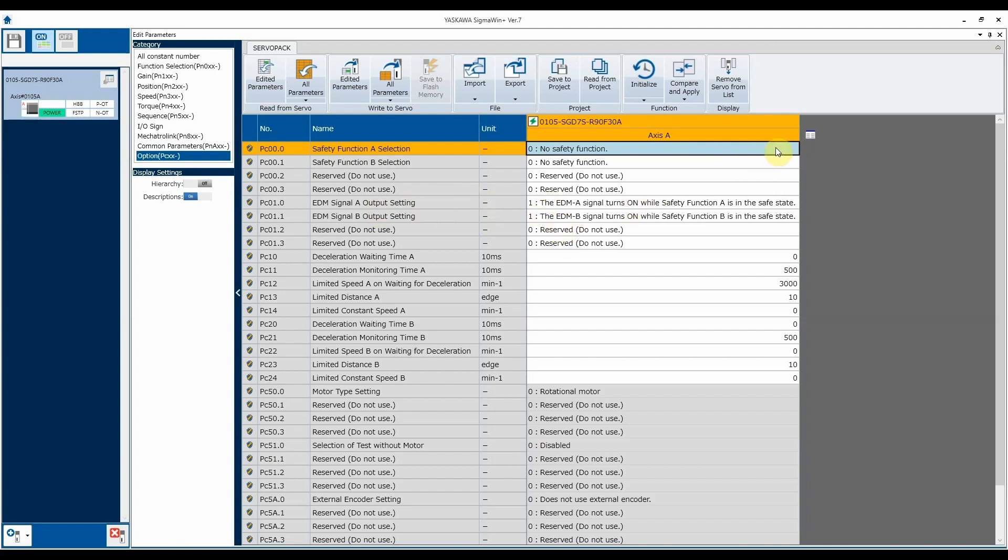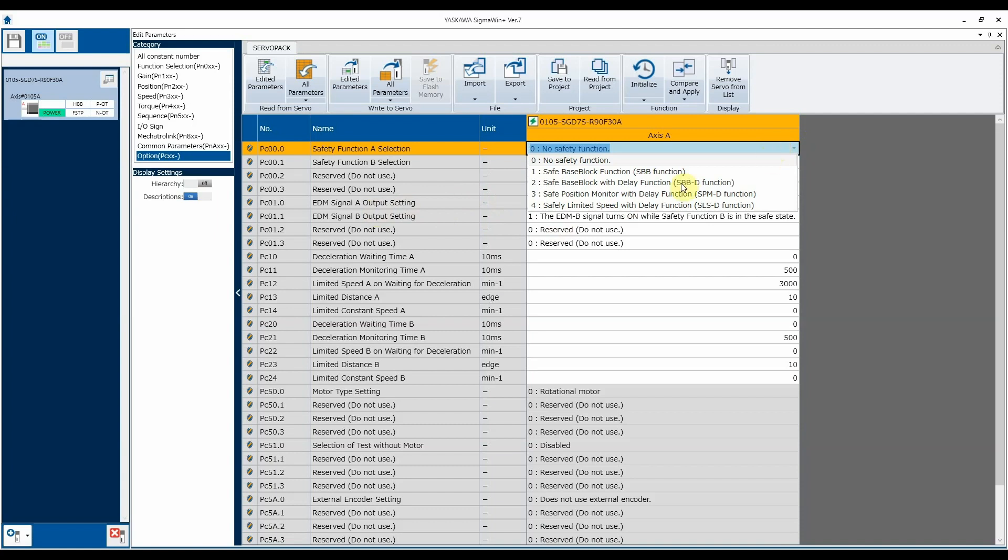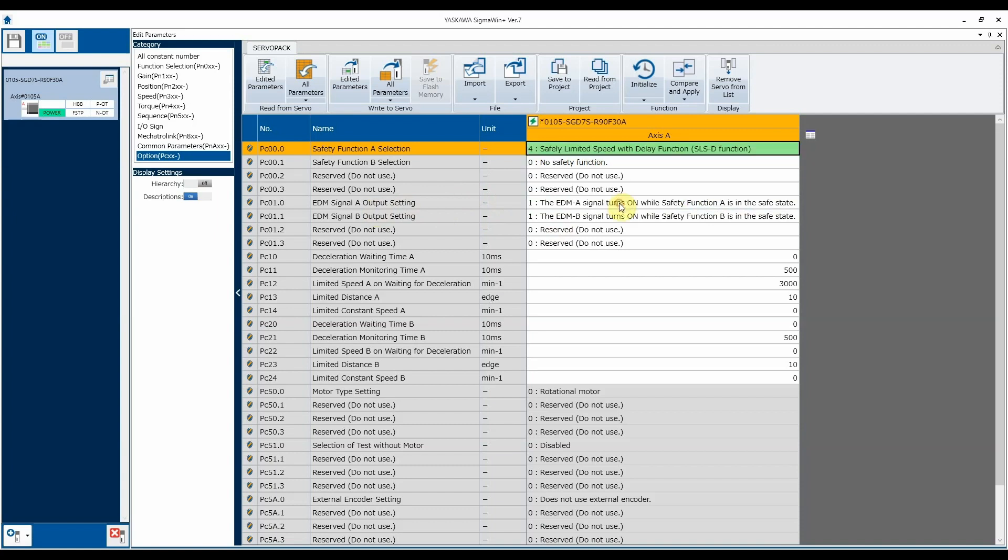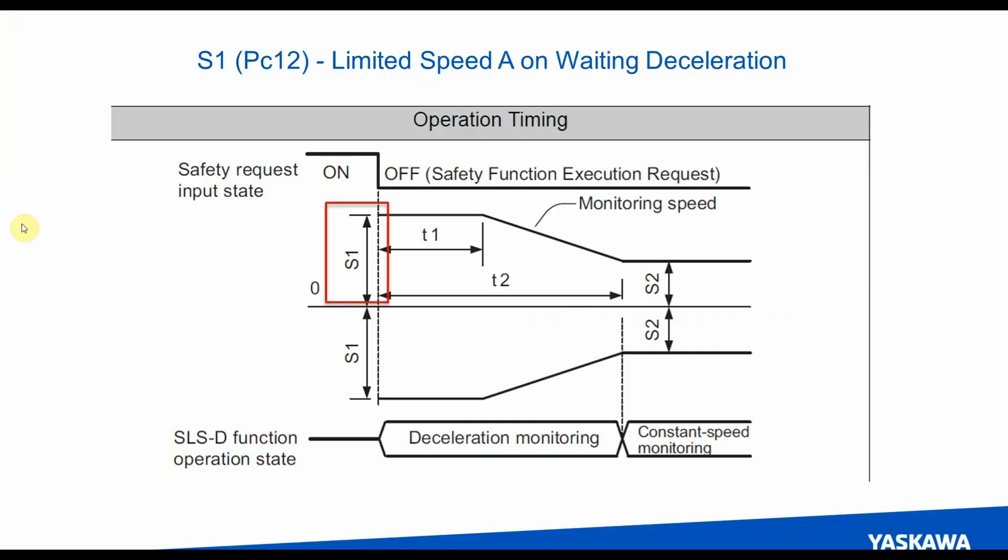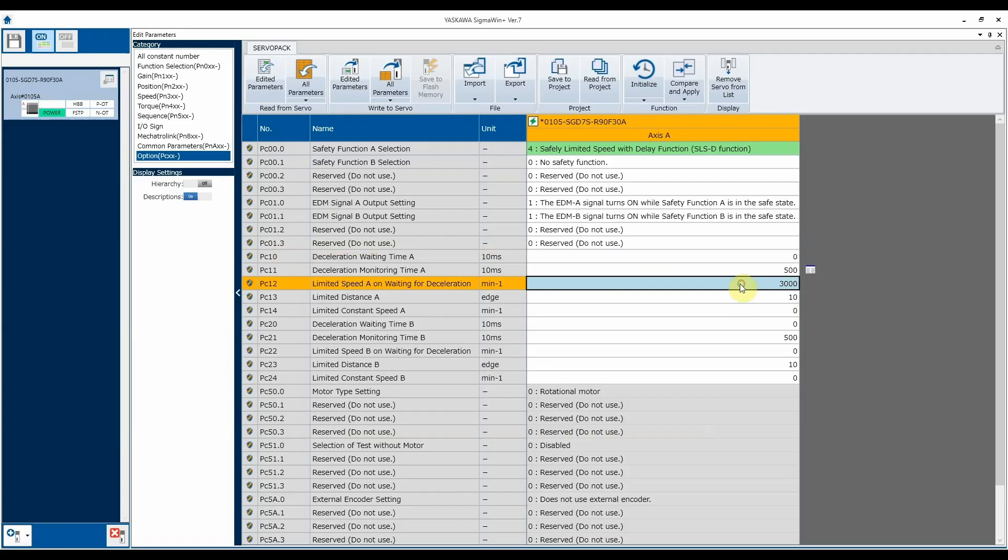One of the first things to do is to enable our functionality. For us, we're going to use our function A as safe limited speed. And then there's four other parameters we need to set based off of time and velocities. The first one's going to be the speed at which the motor's at when the safety input drops requesting safe limited speed. That by default is up at 3000 RPM. We're going to leave that alone for demo purposes, but that can be adjusted.